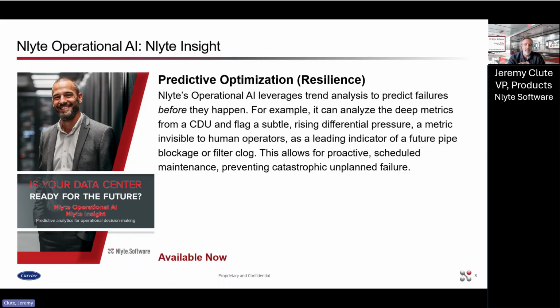Even more importantly, you can use this to modify your thresholds. If you're getting a lot of nuisance alarms on a piece of equipment, going in and out of alarm every minute or so, customers say that creates a lot of operational noise, making it hard to determine what to pay attention to. You want some logic applied automatically so you can change the thresholds on that infrastructure to stop getting an alarm every time it blips in and out within a minute, for instance. A one-minute threshold is usually a great guideline. This is also available today.